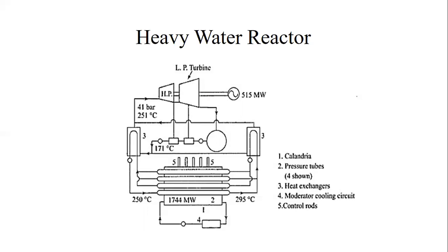The disadvantages of heavy water are its very high cost and, like water, its critical temperature limitations. Heavy water moderated and cooled reactors have been extensively developed in Canada, and on this basis the nuclear power program in that country was built. They are called CANDU PHW, that is Canadian deuterium uranium pressurized heavy water.